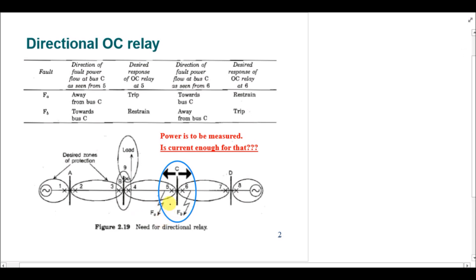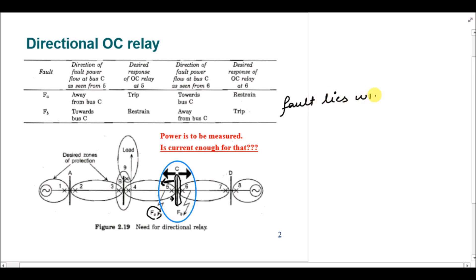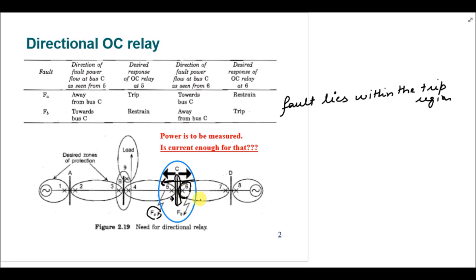We can also determine directionality from the bus bar. In the case of fault FA, the fault current is moving away from the bus bar at circuit breaker five, so that fault lies within the trip region. But for circuit breaker six, the fault power is moving towards the bus, meaning the fault lies in the restrained region. For fault FB, the power direction reverses accordingly for each breaker.